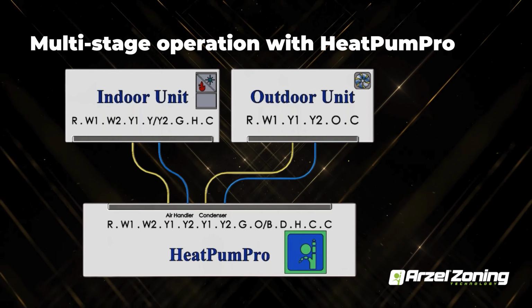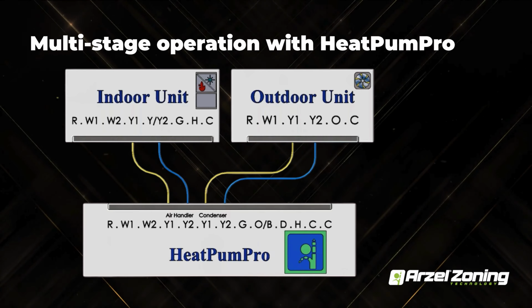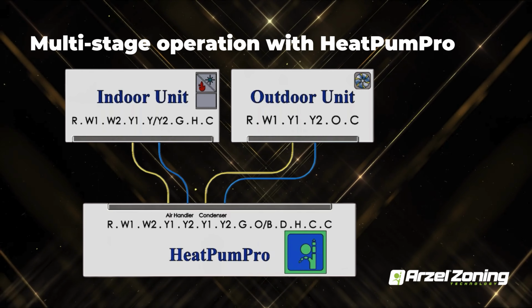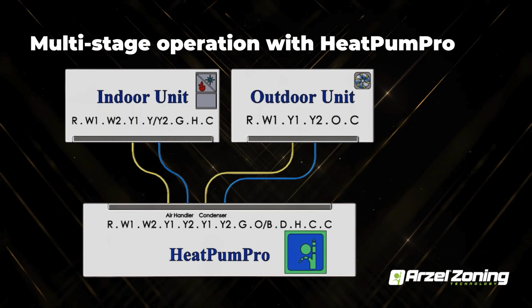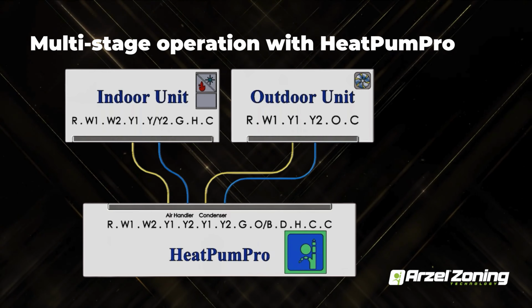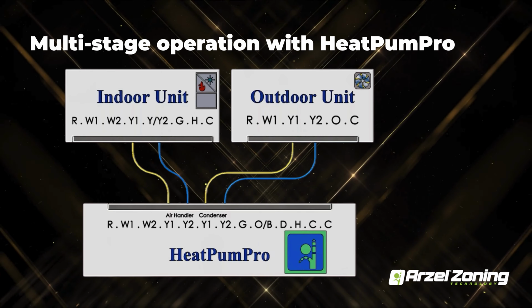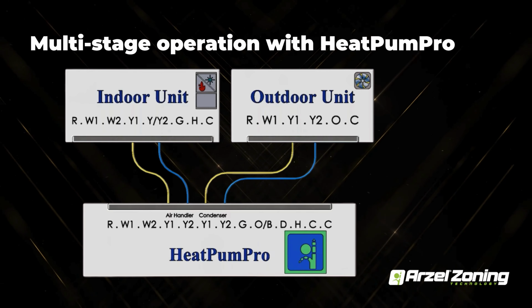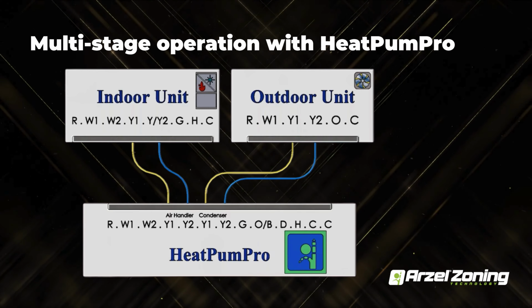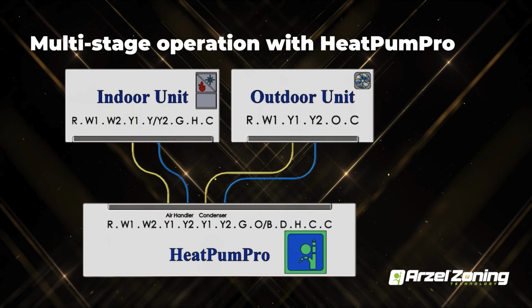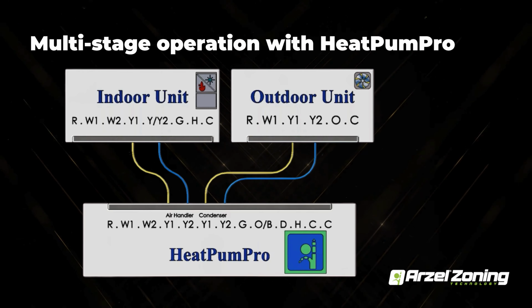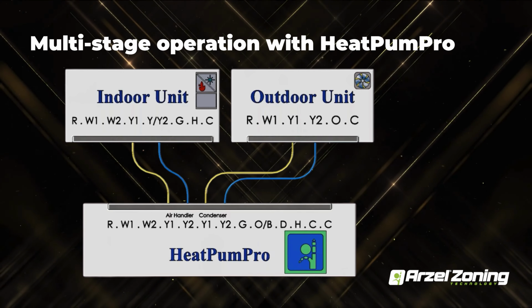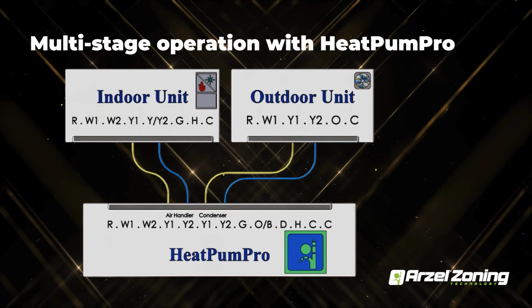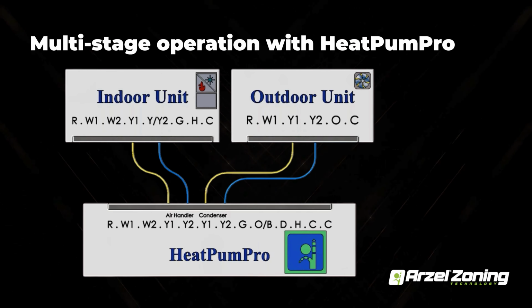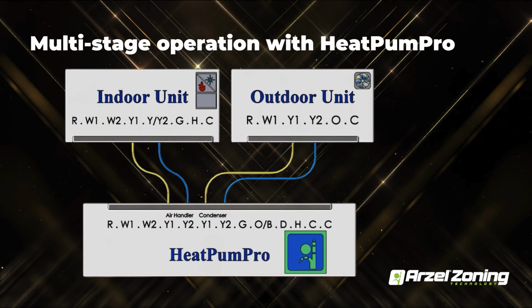So with the HeatPumPro, the way that we handle this is we have separated Y1, Y2 and Y1, Y2 condenser and air handler terminals. So we're able to independently control the staging of your outdoor and indoor unit. And the way the HeatPumPro does this is the indoor unit is all staged based on your zone weighting feature, and we'll get into how that actually operates. And then your outdoor condenser unit, whether it be a heat pump or just a straight AC, it's all done on ductwork temperature and time.